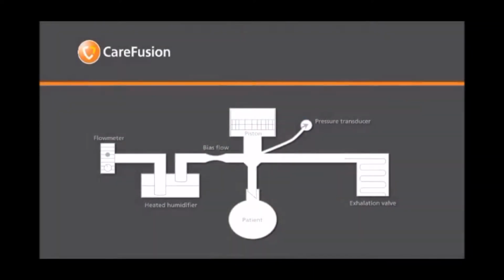This diagram represents a simple schematic of the ventilator circuit. The bias flow enters the system and passes through the humidifier, where it is heated and humidified prior to delivery to the patient. The gas then continues through the circuit to the patient and then out through the exhalation valve. The variable restriction to the outflow of gas generates mean airway pressure, while the piston superimposes the ventilatory process.